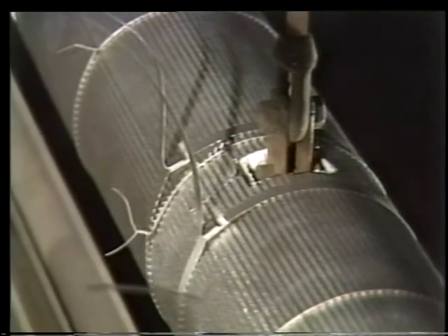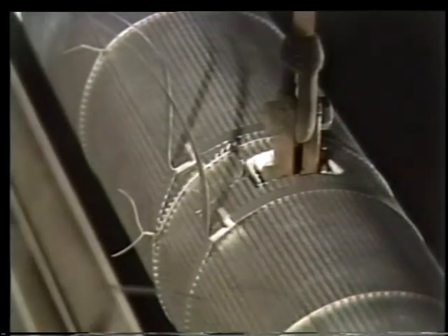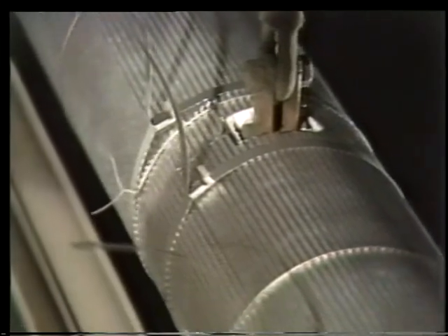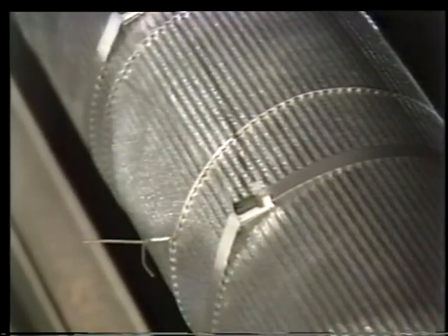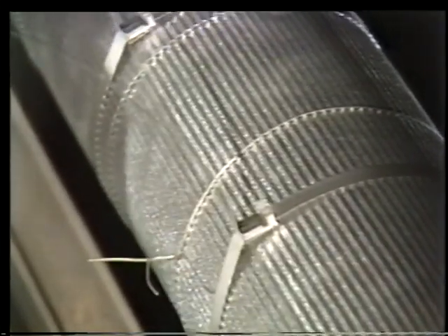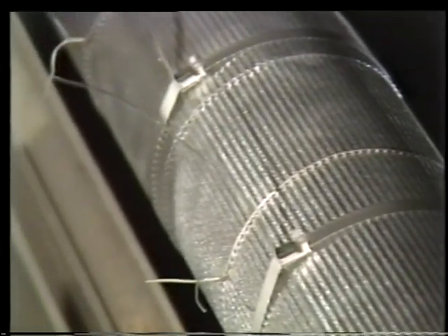At this point, it's not vital to get the bands extremely tight. The banding tool does that. What you want to do here is position the bands correctly and secure them loosely over the whole jacket. Just slip the band around the jacket, pull it tight, and bend the end up to hold it in place. Don't bend the soft metal back and forth unnecessarily. Metal fatigue will cause it to snap.